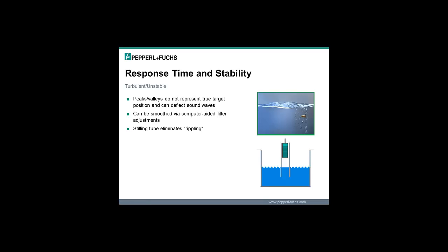One of the reasons an ultrasonic might use this averaging function is to improve the stability. So if you're looking at perhaps an agitated tank of whatever, water, beer, cleaning solutions, you're going to get peaks and valleys because that surface is going up and down. But you just want to basically know the average of the output. You don't want to know the peak and valley of every little wave and ripple. So that's one of the reasons why an ultrasonic sensor will average a series of echoes and then provide an output. It's to make for a smoother output in instances like level control.